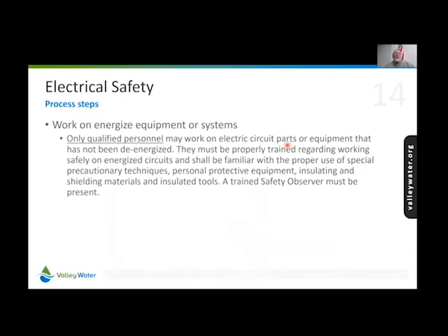Work on energized equipment or systems: we want to remind everybody that only qualified personnel may work on electric circuit parts or equipment that has not been de-energized. They must be properly trained regarding working safely on energized circuits and shall be familiar with the proper use of special precautionary techniques, personal protective equipment, insulating and shielding materials, and insulated tools. A trained safety observer must be present.